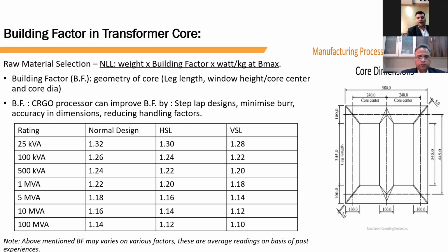In this table, these are some average readings based on past experience in this industry. I'm giving one comparison of how building factor varies from 25 kVA to 100 MVA transformers. In small rating transformers, building factor will be high because the ratio of leg length, window height, and core center is different compared to large power transformers.